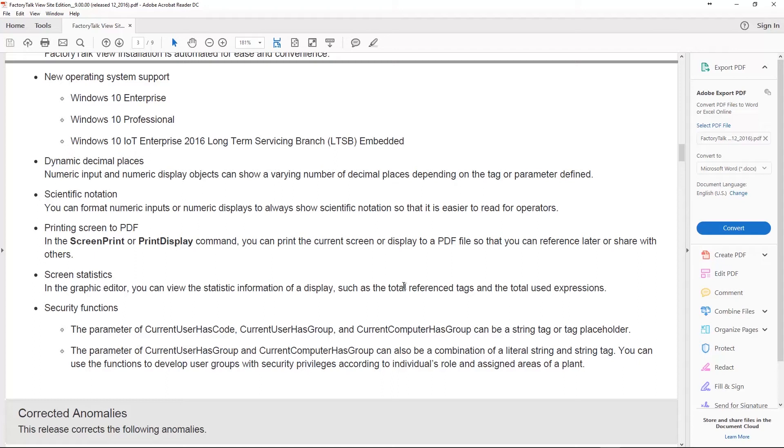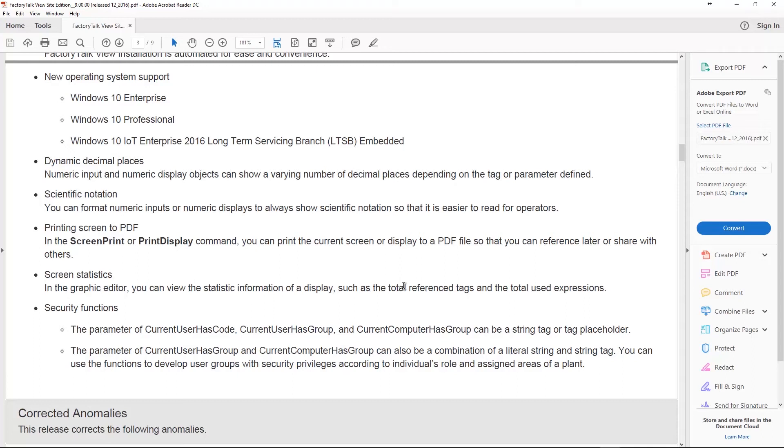Some other things here, printing to PDF, that is awesome. So now the screen print or print display command can print your screen or display to a PDF file. That's pretty awesome. In addition to that they've added some screen statistics inside the graphic editor so you can see total number of reference tags, total number of used expressions. And they even enhanced some of the security functions so now the function current user has code, current user has group and current computer has group can have a parameter that's a string tag or a placeholder. That's cool.